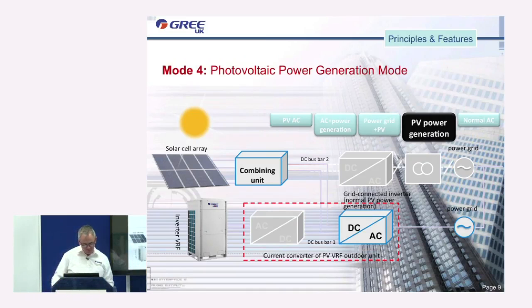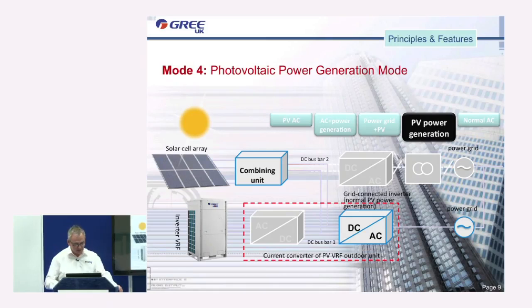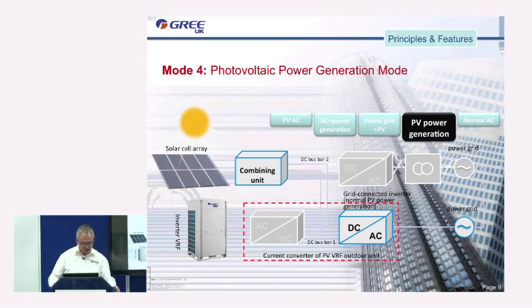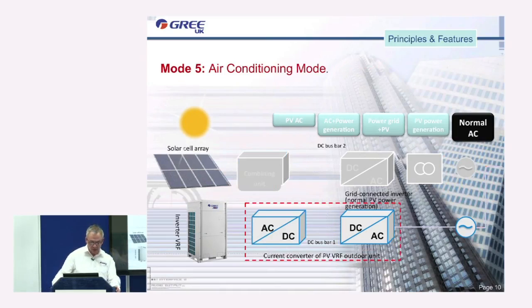Then we have mode 4, which is when the PV VRF system is not in operation. And in this case, any power generated by the solar array can be literally via the unit directed back through into the grid, into the main AC power supply. Again, no additional components required, already all connected, so we can now be feeding back into the grid. And then finally mode 5, this is when there's no PV power generated at all, so therefore we just use the grid power as with a normal VRF system.